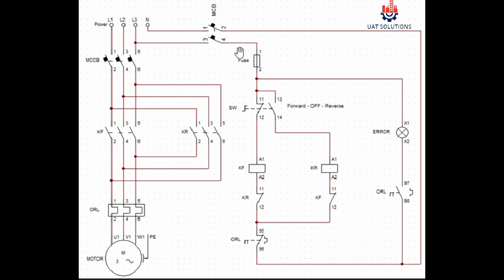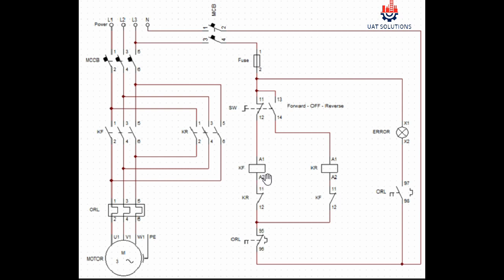While the neutral comes from overload point 95 to the closed contact of contactor KR 12 and 11 to the coil terminal A2 of contactor KF, and the contactor energizes and motor starts to run in forward function.